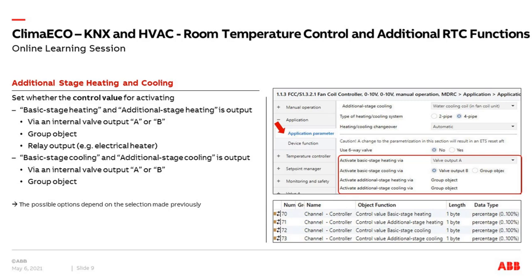Assigning these stages to the hardware: in our fan coil controller you can activate basic stage heating via valve output A and basic stage cooling via valve output B. For the additional stage heating or cooling, if you need both, there are no additional hardware outputs in this device, so you have to send it via a group object to an additional valve controller to control in total four different circuits. You can also route basic stage heating or cooling this way — you are completely flexible, but in principle you need at least two additional outputs if you have four circuits.